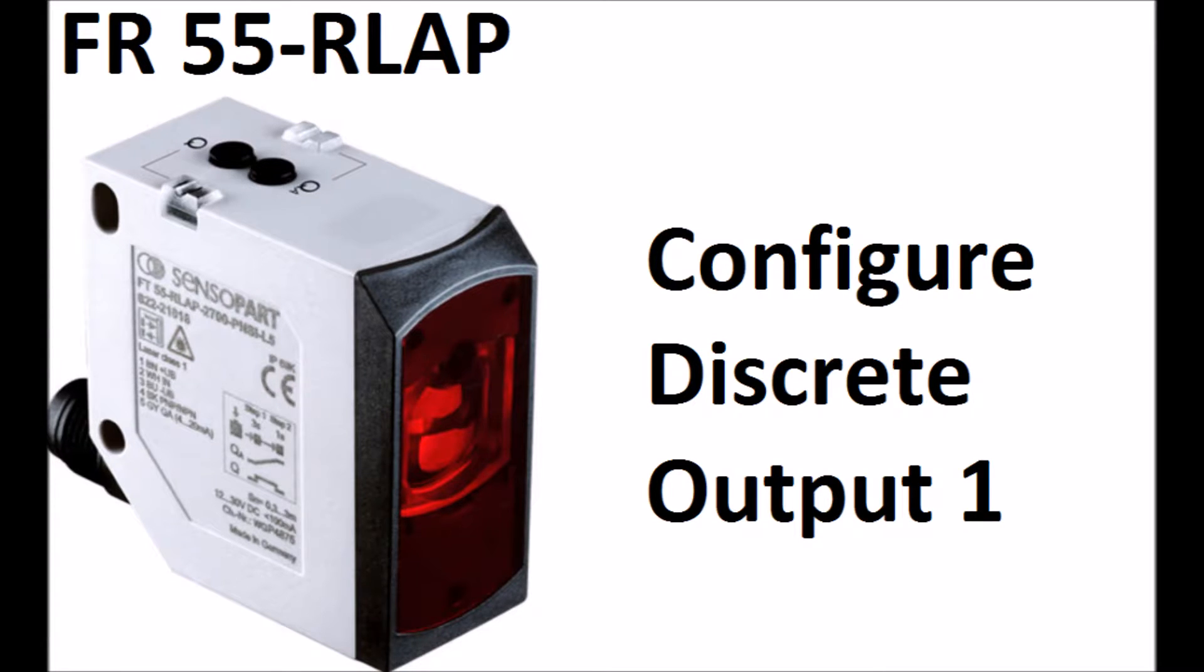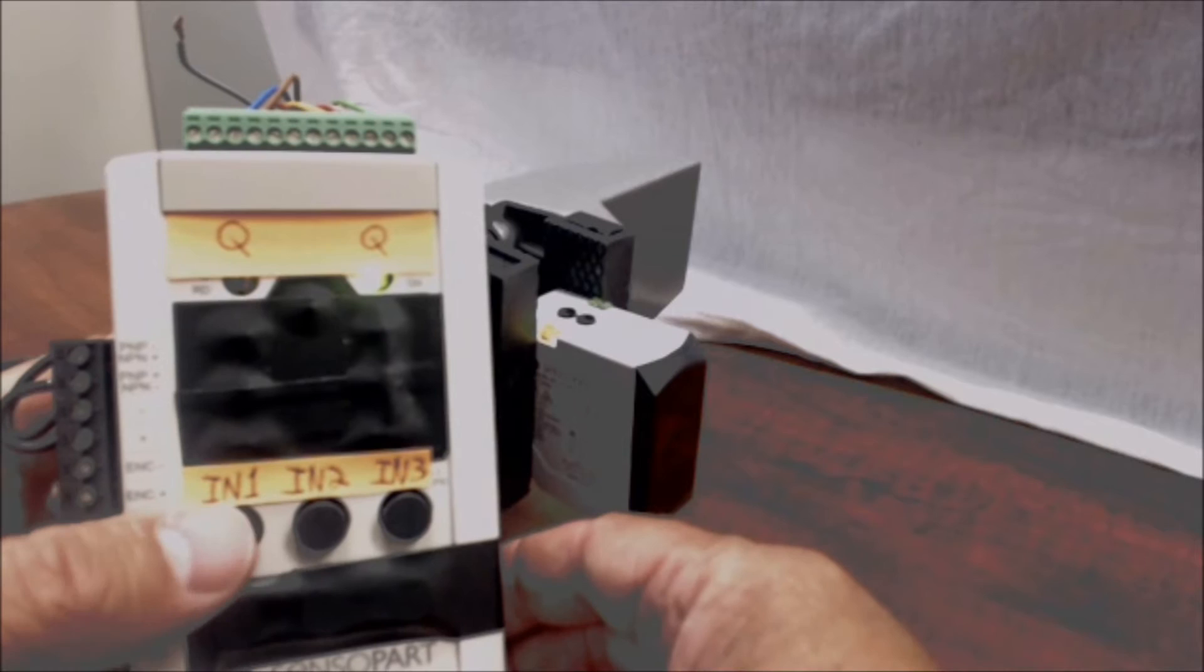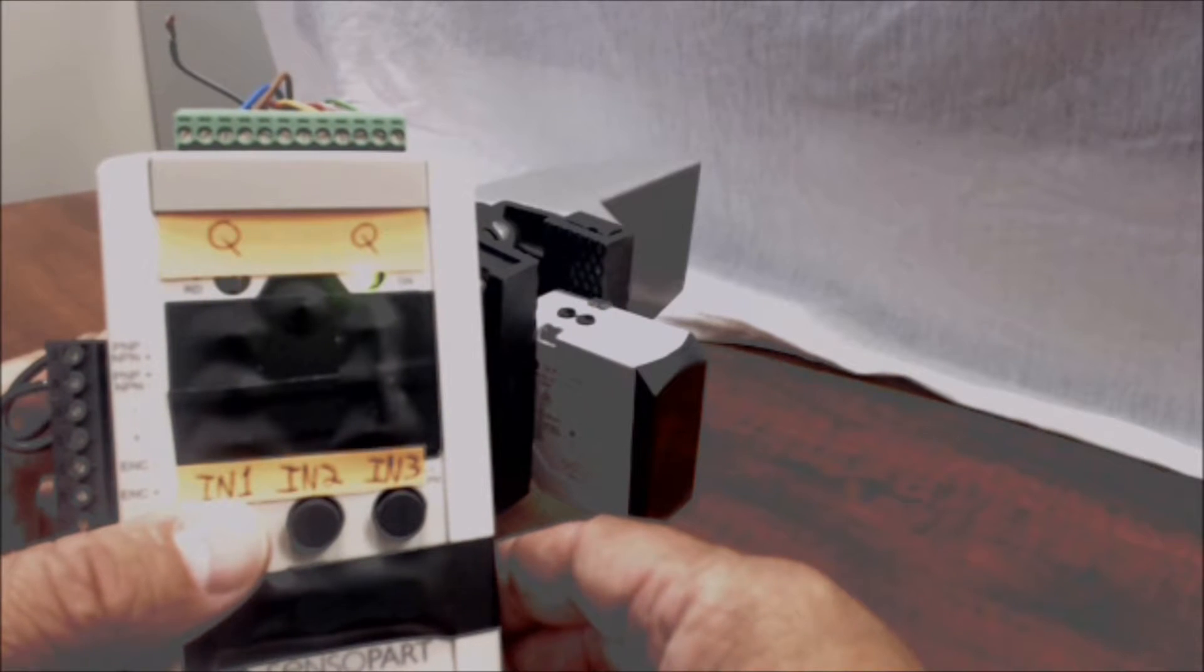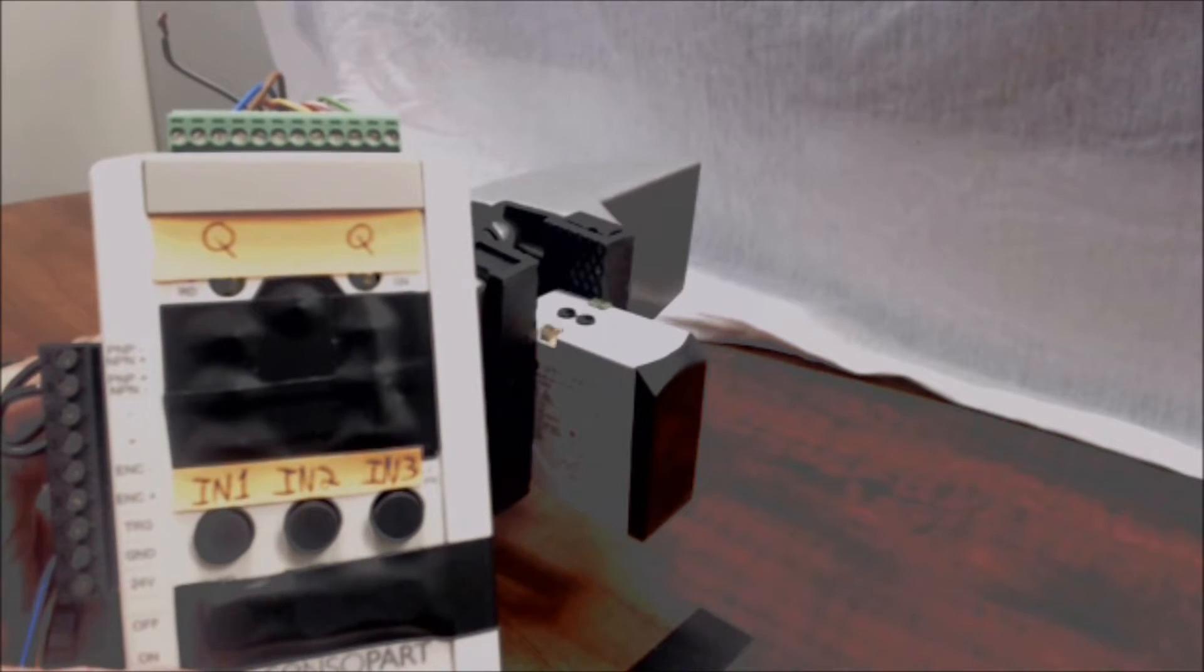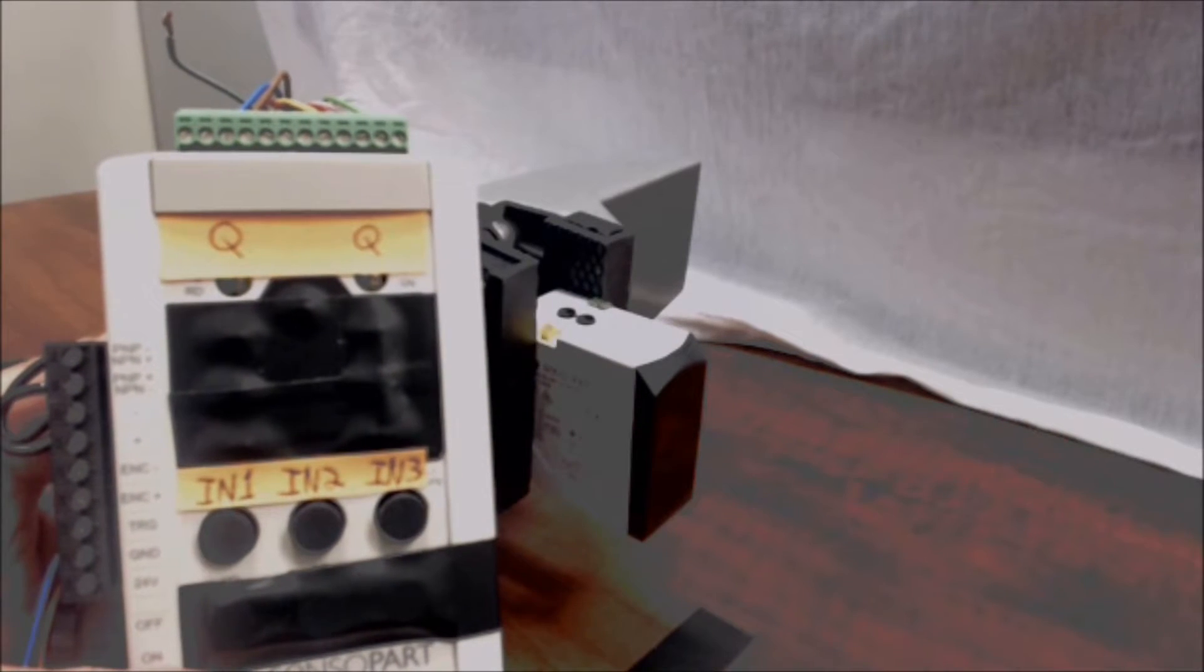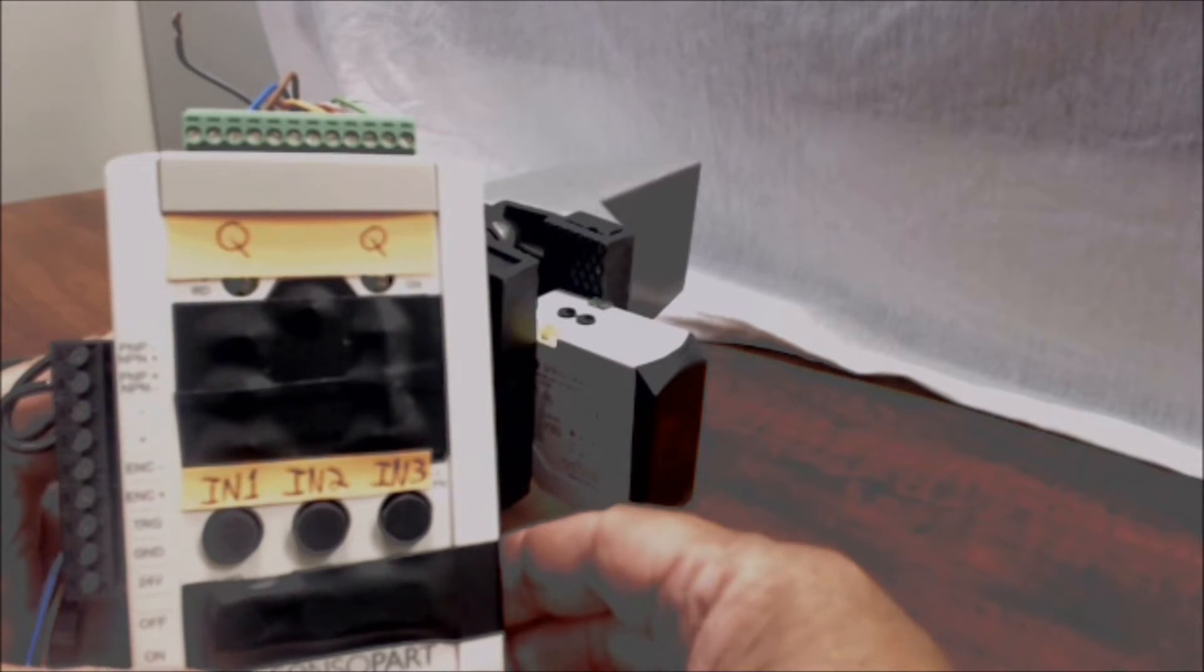Teaching the discrete output in window mode is the same as the analog. You just use the other teach button or the other input. So here, we'll press and hold the other input for more than three seconds. We'll watch the sensor until the lights flash. There we go. Now, we'll move the target to the next position, and then we'll tap the button. And here we go. Tap. Sensor's taught.